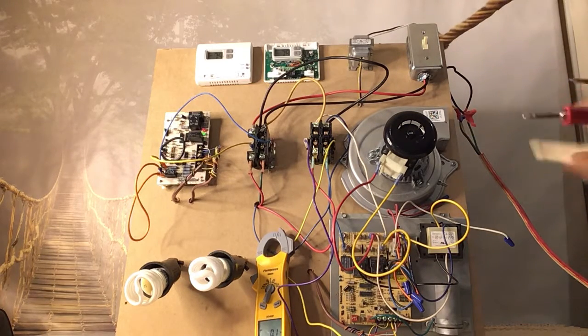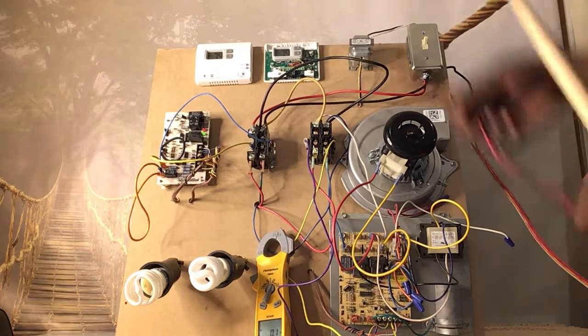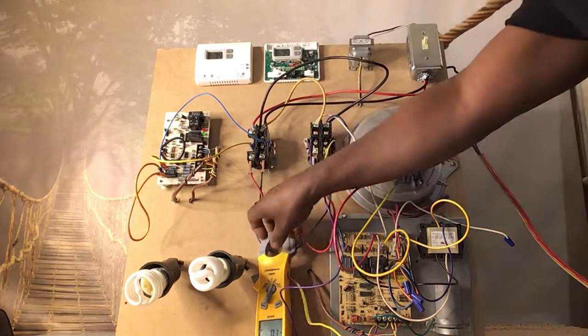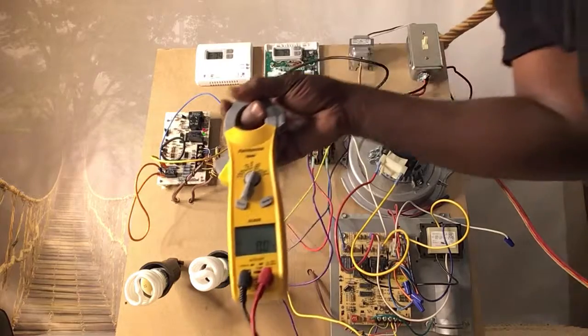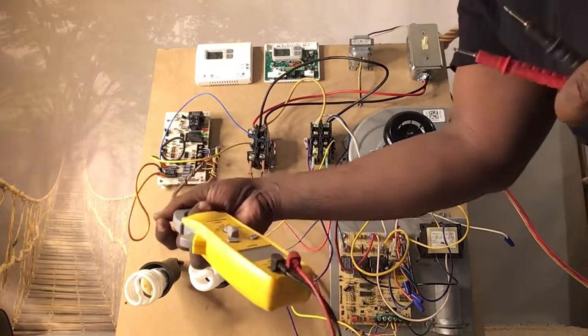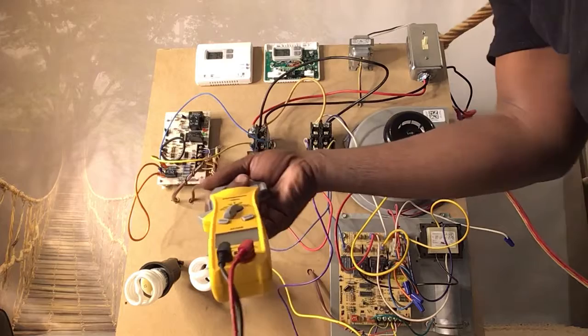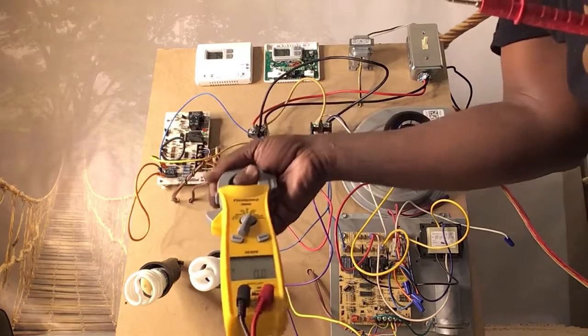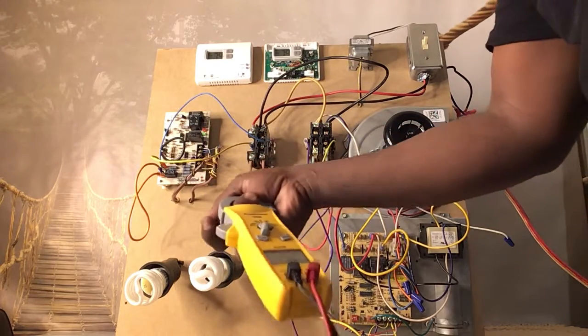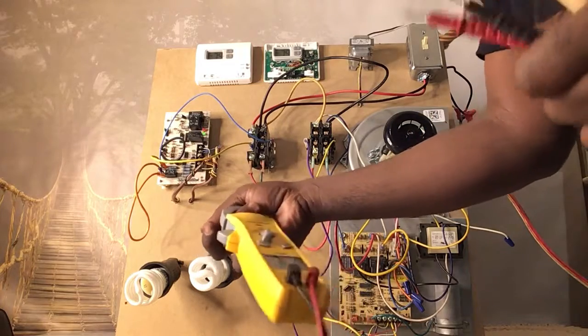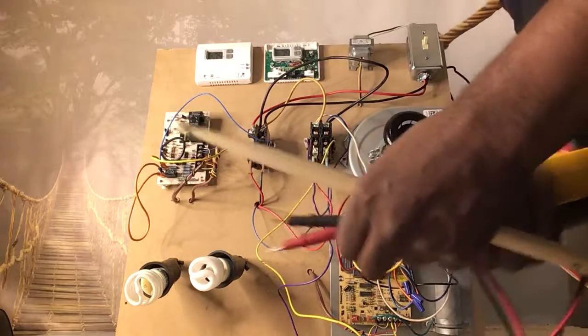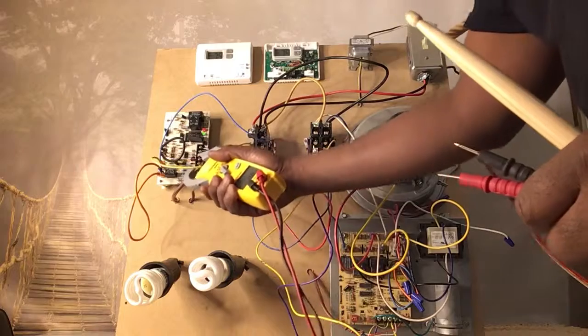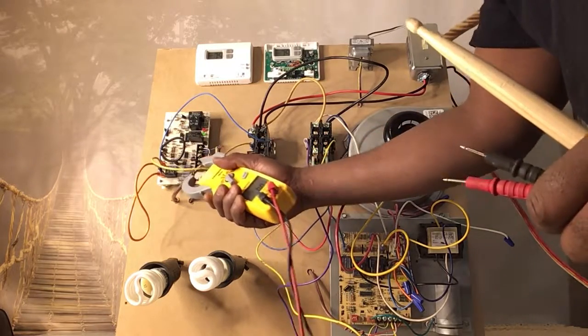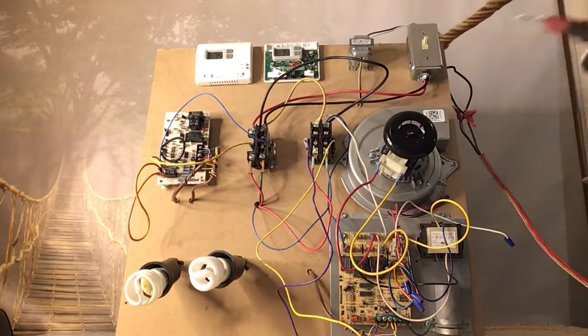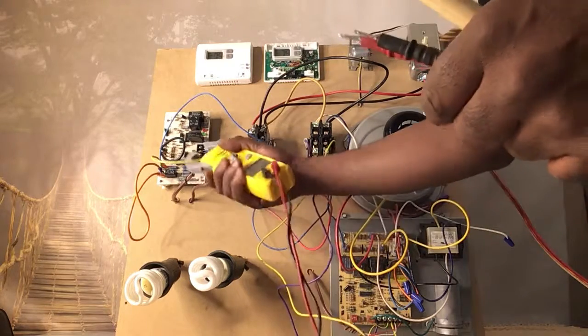So at the end of the day, volts AC. This is your meter. Simple meter, nothing serious. This one right here is a Fieldpiece. I probably spent maybe $70 on it, but it's good for residential checking AC voltage. Also has a pretty cool amp clamp on it. Probably get into that a little bit later, but you clamp that on there. Once you get the load that you're trying to run, you can determine how many amps it's actually drawing by using this amp clamp.